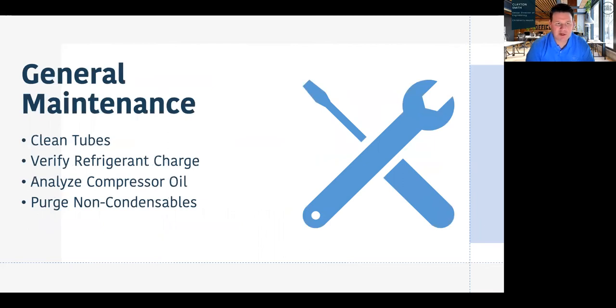Finally, just some simple general maintenance items that I feel like we all know, but we need to continue to reinforce. One, a clean tube's a happy tube, right? If your chiller has clean tubes, it's going to run like a top. If they get nasty and fouled, your efficiency just drops. Second, verify your refrigerant charge. How much more compressor energy is being used because we have the wrong amount of refrigerant, either too much or too little? So verify that the refrigerant is charged appropriately. Analyze compressor oil: perform a chemical analysis on the oil to provide details about the moisture content. High moisture levels could indicate a purge problem. And finally, purge non-condensables. Those non-condensables can reduce chiller efficiency by almost 5%.